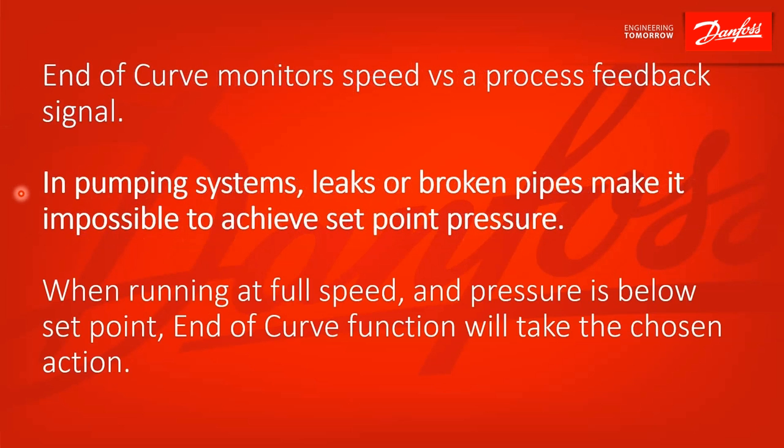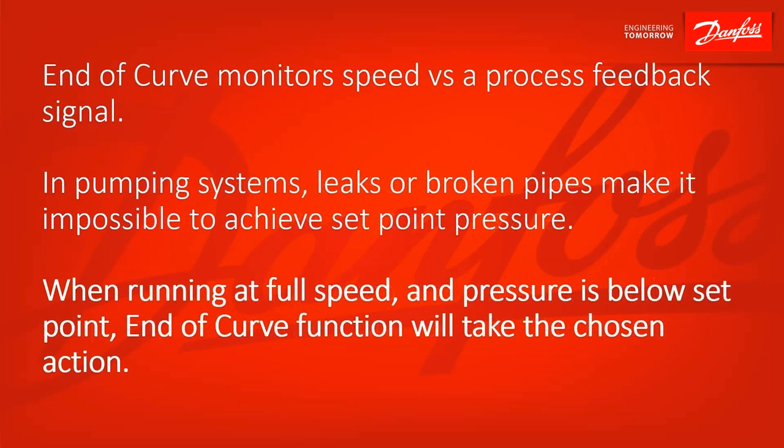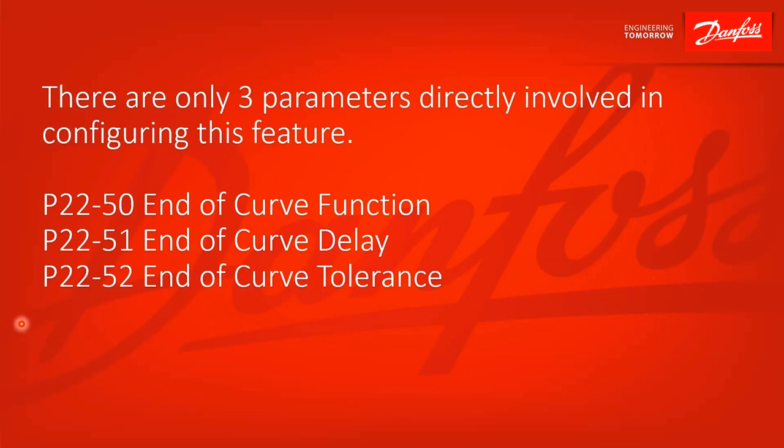In pumping systems, leaks or broken pipes make it impossible to achieve set point pressure. So if a drive is running at full speed and pressure is below the set point, end of curve function will take the chosen action. There's only three parameters directly involved in configuring this feature.